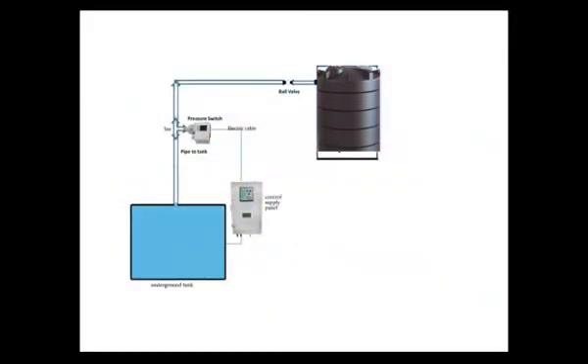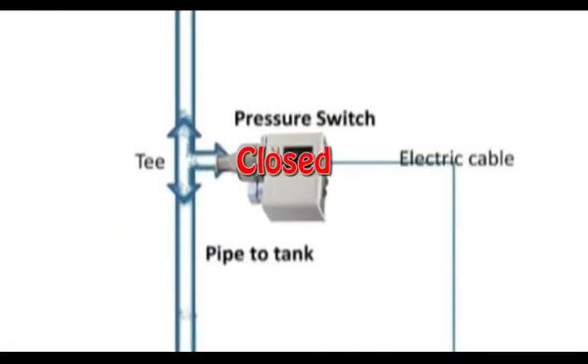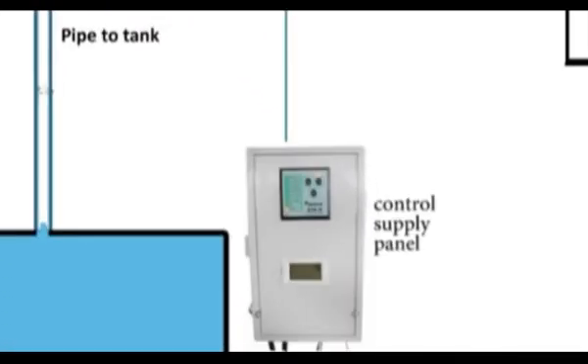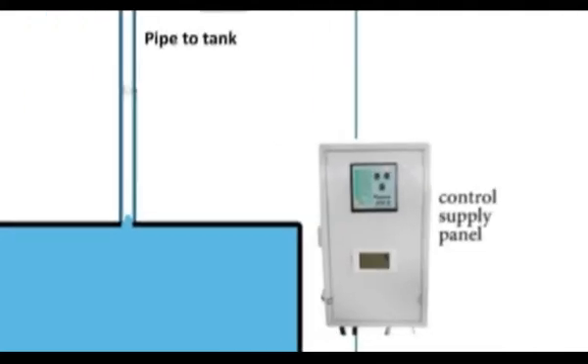Initial condition, suppose tank is in empty condition. Pressure switch contact is in close condition. Control supply will pass through pressure switch contact and will start pump.